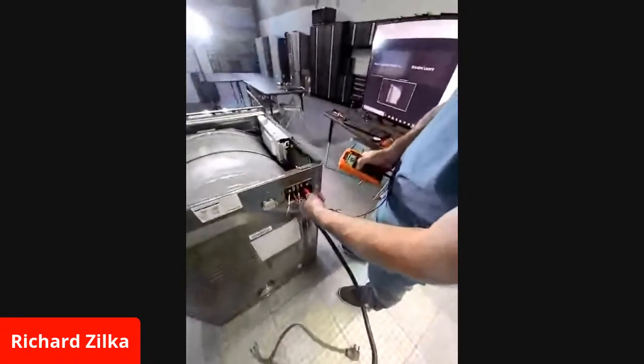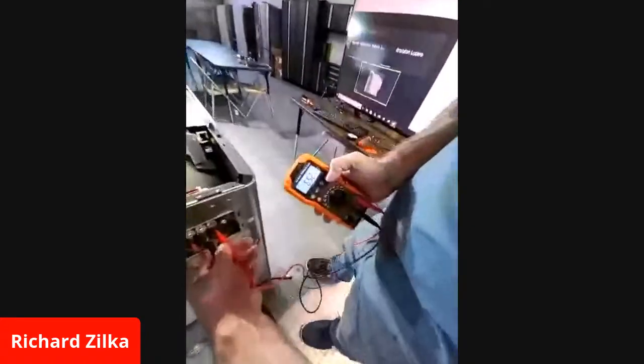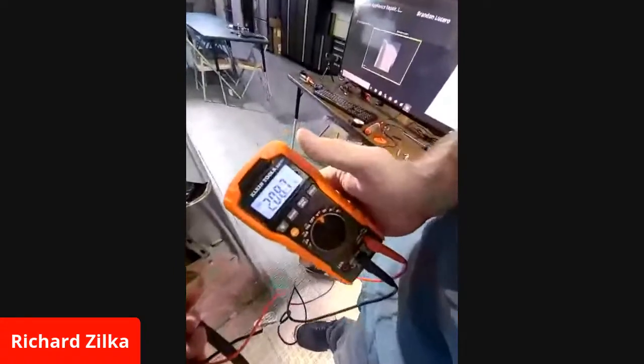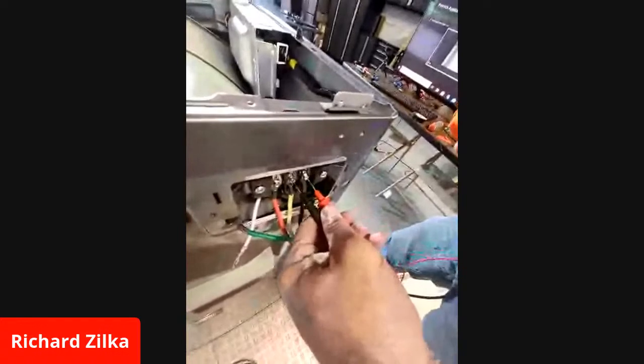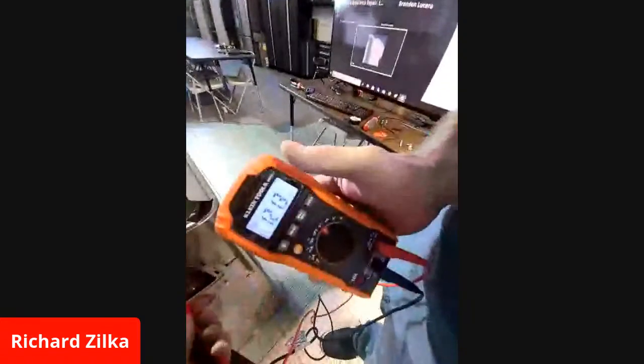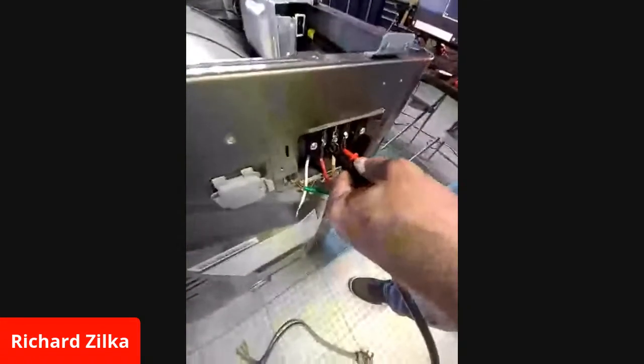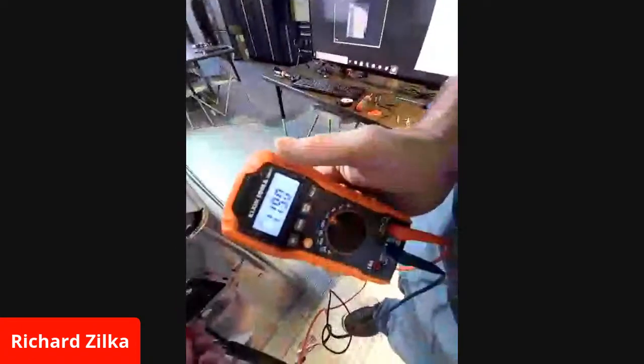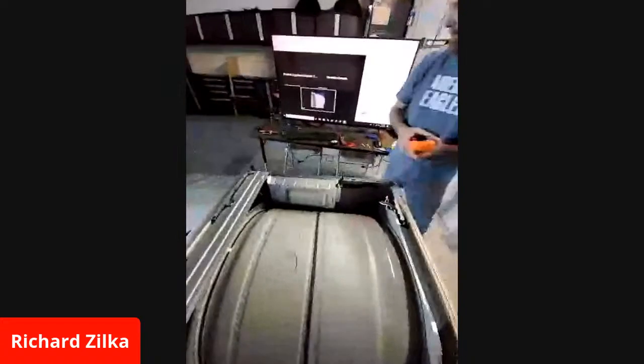I'm going to go ahead and check power coming in. I'm going to check line 1 to line 2. I got 208 volts coming in. I'm going to check line 1 to neutral, I got 120. I'm going to check line 2 to neutral, I got 120. Let's go back to the board and make sure I connected everything properly.